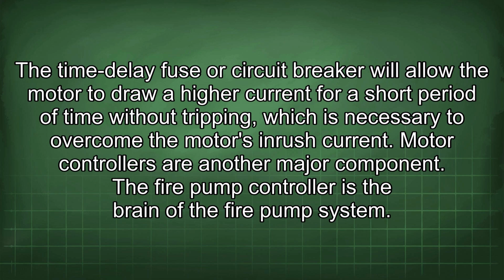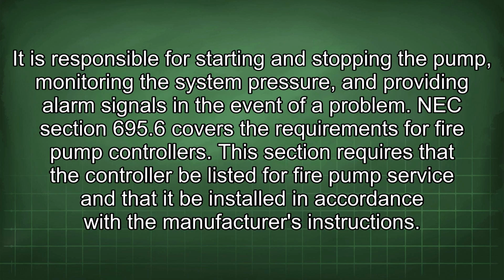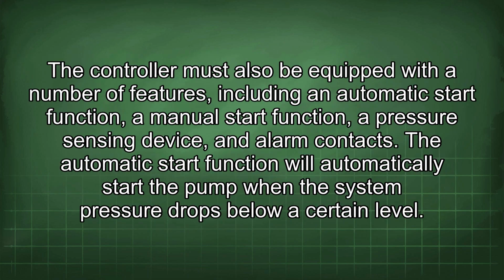Motor controllers are another major component. The fire pump controller is the brain of the fire pump system. It is responsible for starting and stopping the pump, monitoring the system pressure, and providing alarm signals in the event of a problem. NEC section 695.6 covers the requirements for fire pump controllers. This section requires that the controller be listed for fire pump service and that it be installed in accordance with the manufacturer's instructions. The controller must also be equipped with a number of features, including an automatic start function, a manual start function, a pressure sensing device, and alarm contacts.